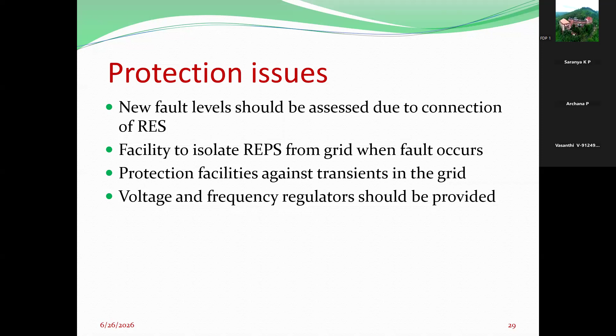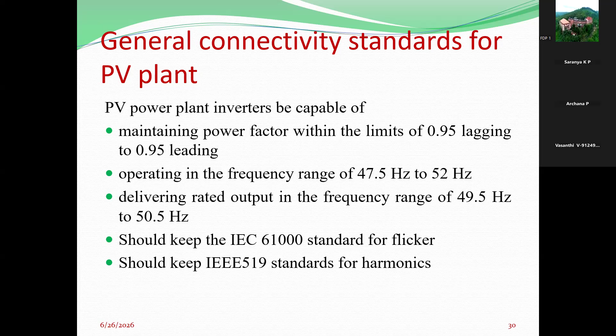So these are some of the connectivity standards. PV power plant inverters should be capable of maintaining a power factor within the limits of 0.95 lagging to 0.95 leading. Then it should operate in the frequency range of 47.5 to 52 Hertz. Then it should deliver a rated output in the frequency range of 49.5 to 50.5 Hertz. Then it should keep to the IEC standard 61000 for flicker and IEEE 519 for harmonics.